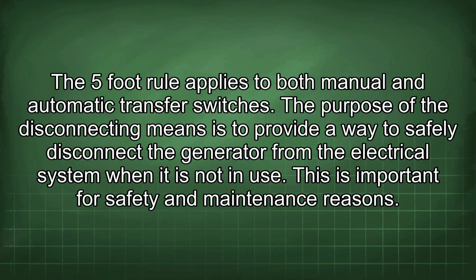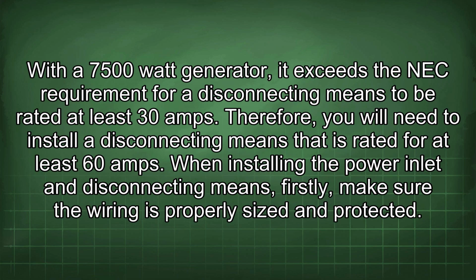The purpose of the disconnecting means is to provide a way to safely disconnect the generator from the electrical system when it is not in use. This is important for safety and maintenance reasons. With the 7,500 watt generator, it exceeds the NEC requirement for disconnecting means to be rated at least 30 amps. Therefore, you will need to install a disconnecting means that is rated for at least 60 amps.